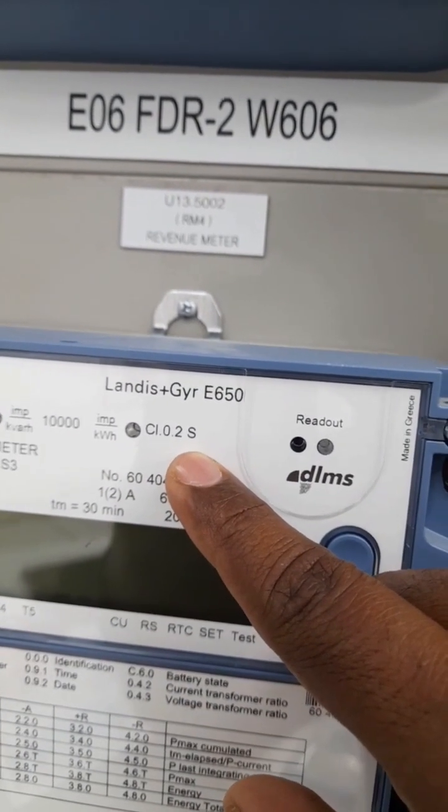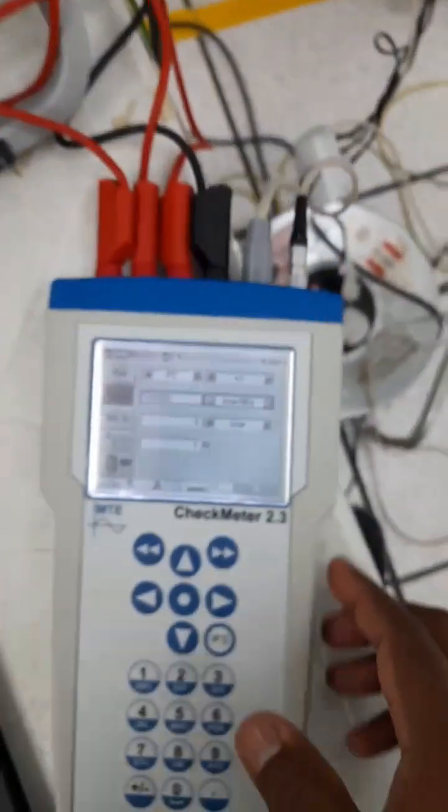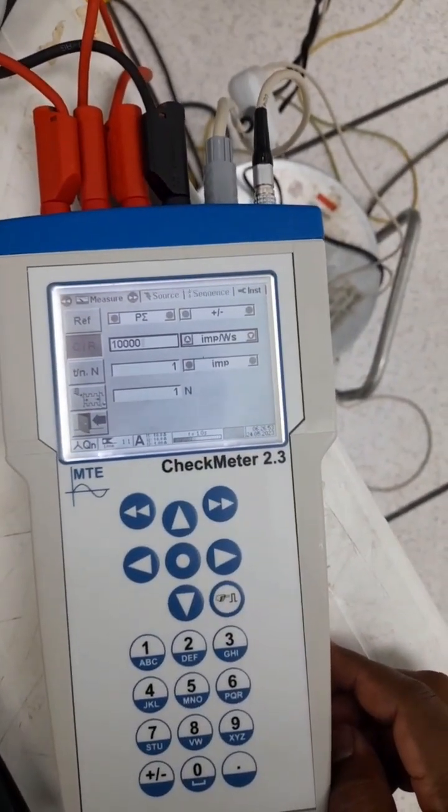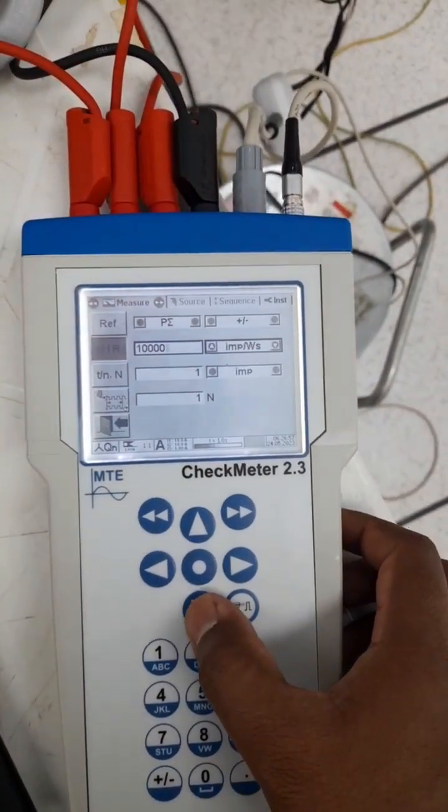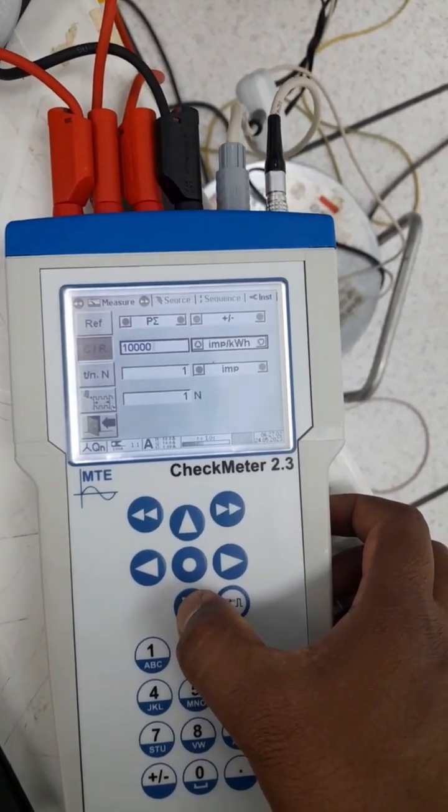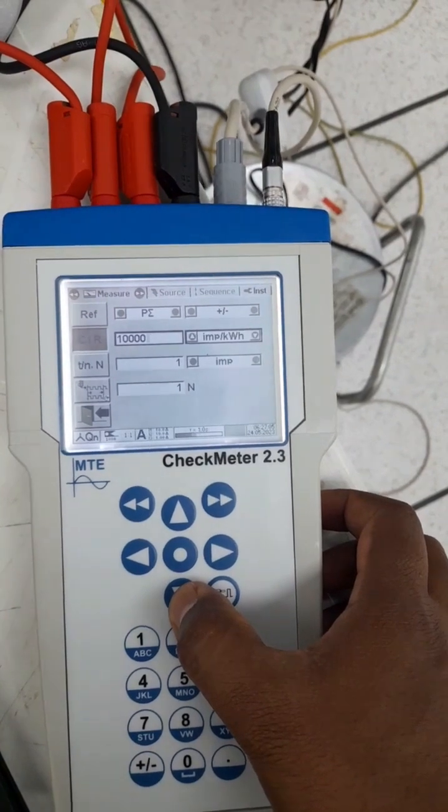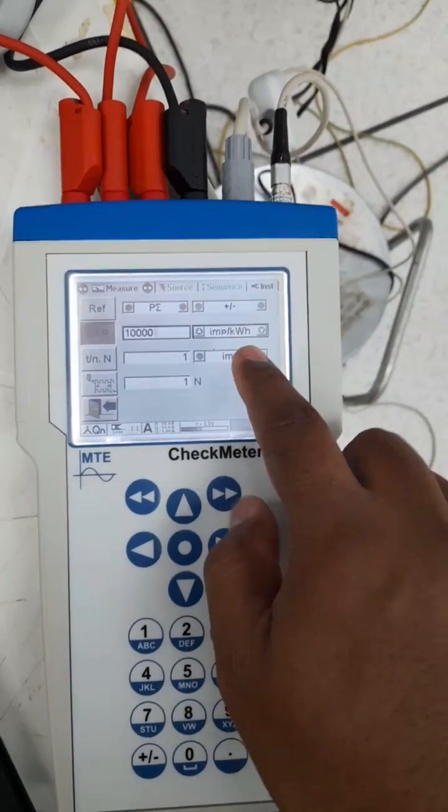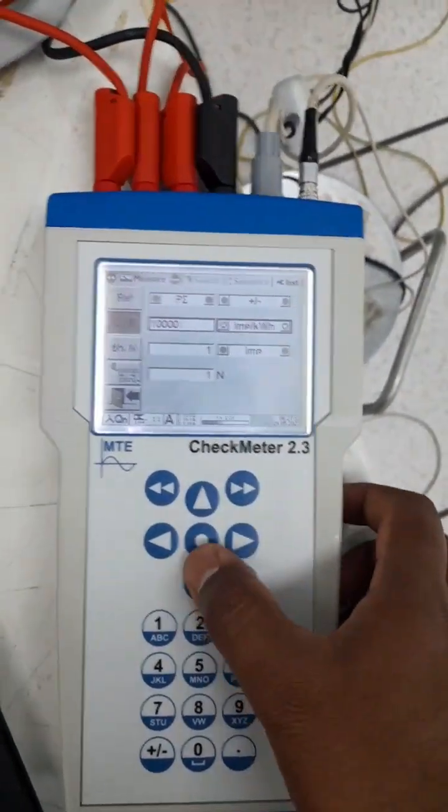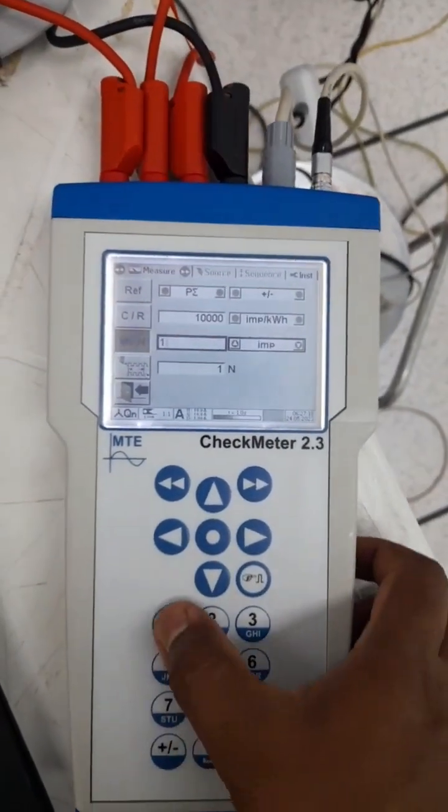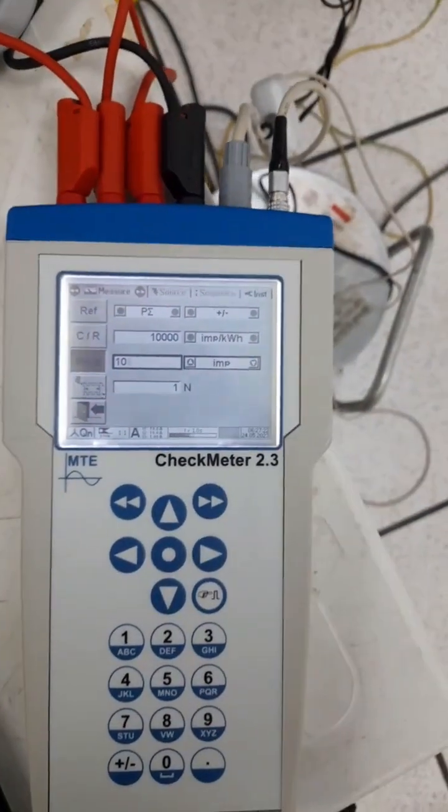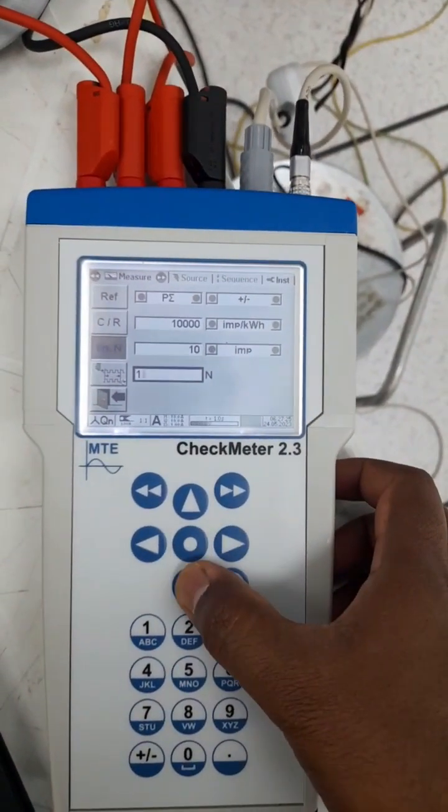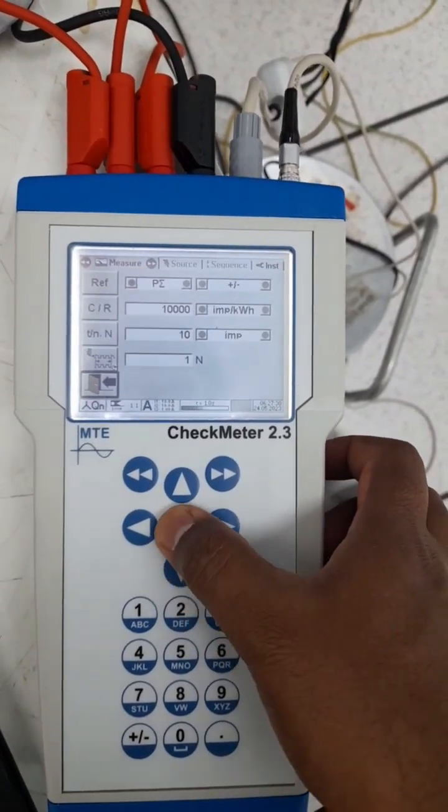Now I set this meter constant 10,000 as per the meter nameplate. This option is also very important. Now I'm catching pulse to check the accuracy for kWh, so this option should be impulse per kWh. Once you're done, just press enter and come down. Here you have to set the impulse, how many impulses you have to catch. Based on that, it will calculate the power and show you. No need to change or do any changes over there. Come down, go back.